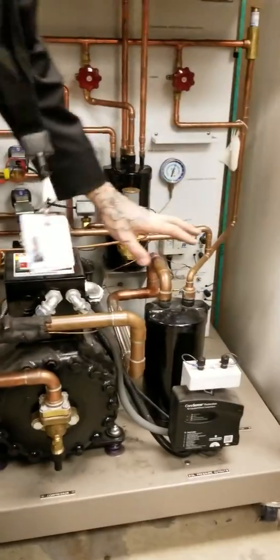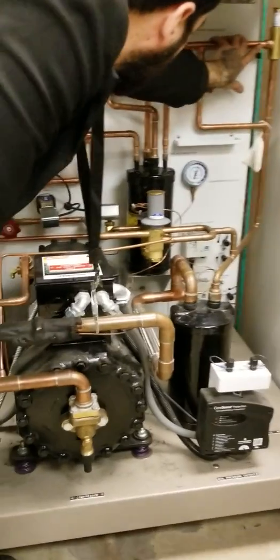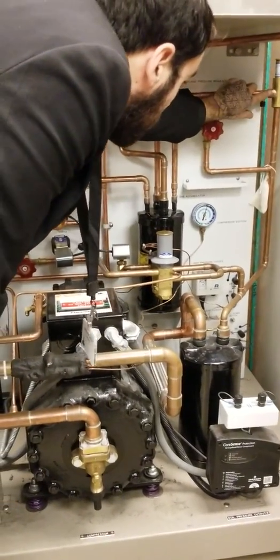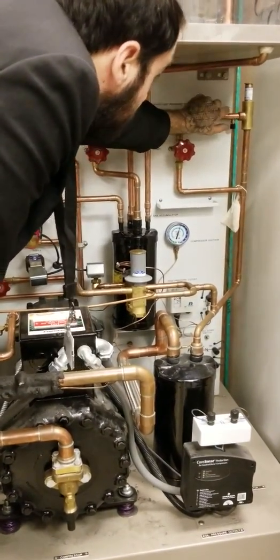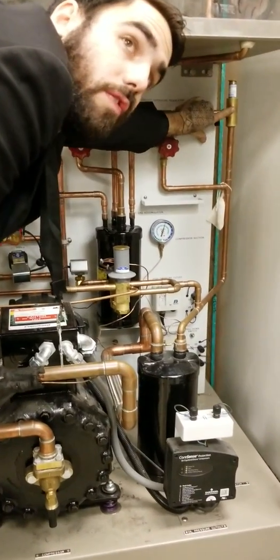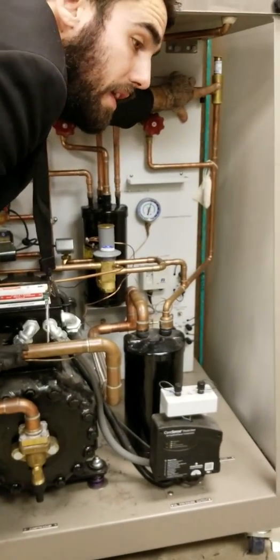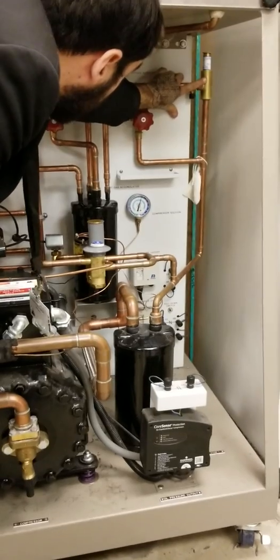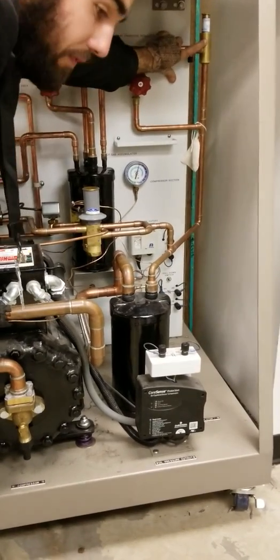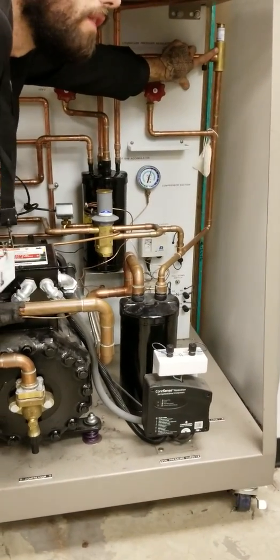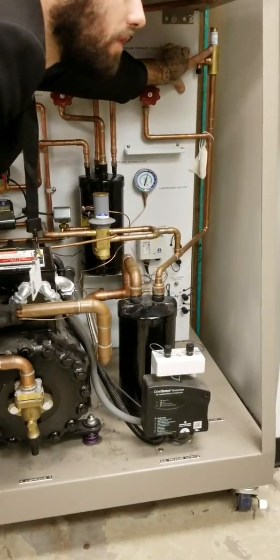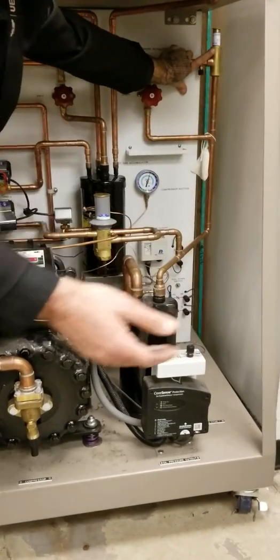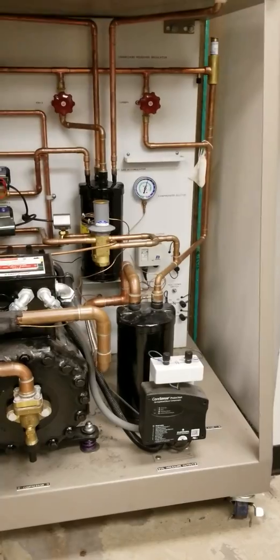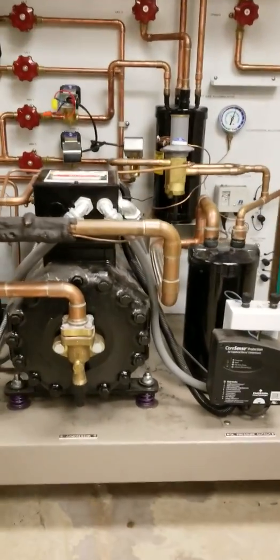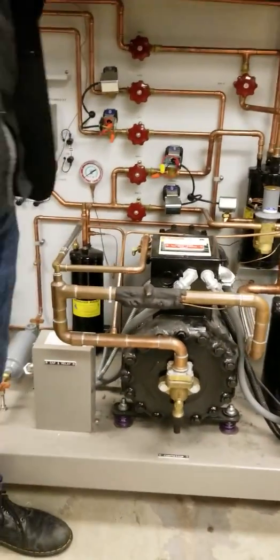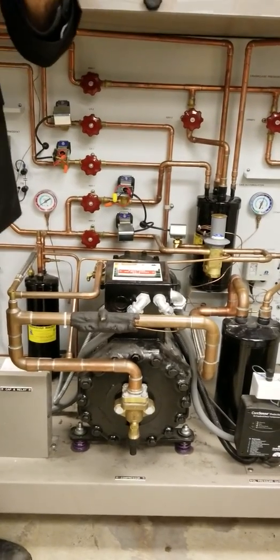Then the system's pretty normal. You have an evaporator pressure regulator, so you can control the pressure inside each evaporator. It basically works kind of like a check valve, or an automatic expansion valve, where it only allows a certain amount of pressure out of it. If you set it to 35 psi, anything more than 35 is going to push it open and allow it out.